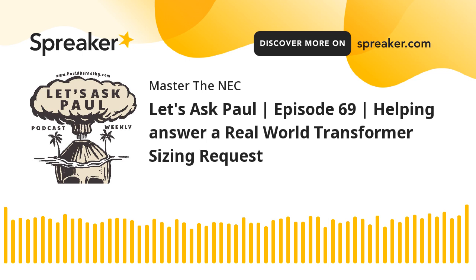And it's assuming that you've already done all this and you're telling me that at the end of the day, it's 78 amps because that's all you've given me. I don't know anything else than that. So we're just gonna go with the 78 amps. So a lot of times the 45 kVA might be the best option. It does give you a little bit more capacity.